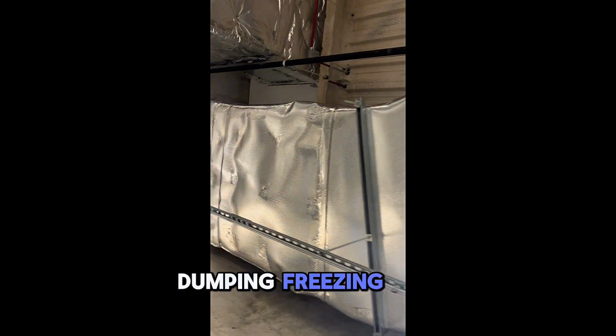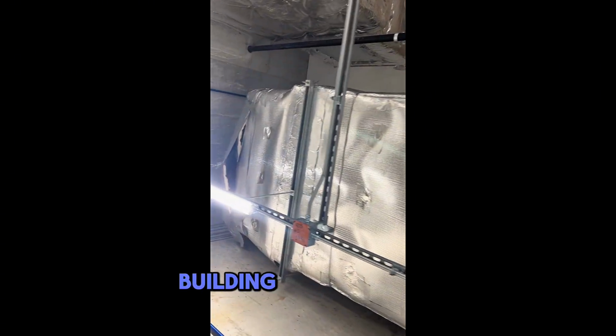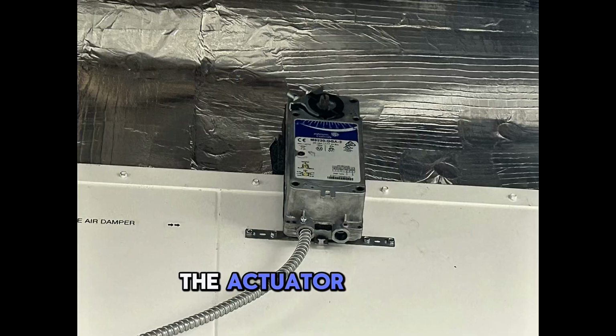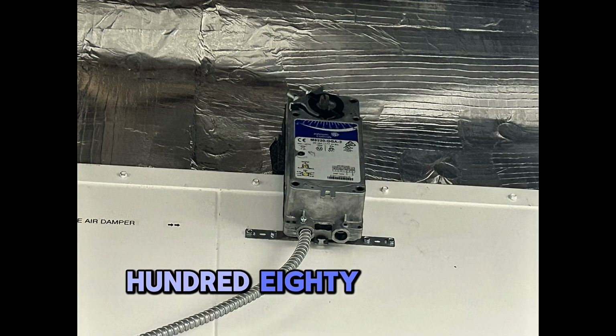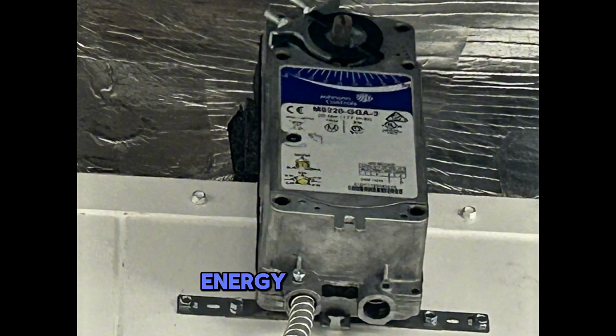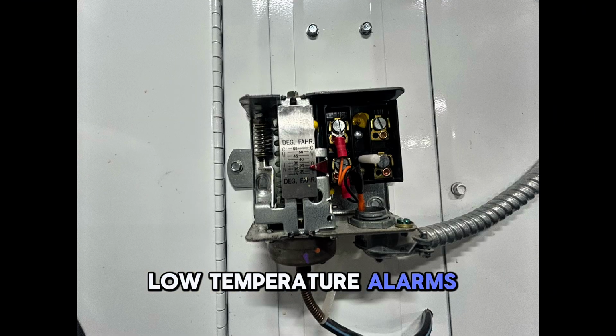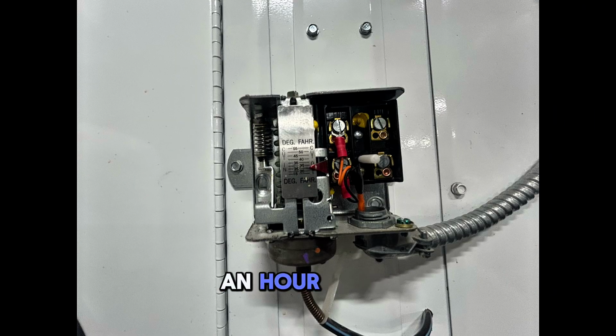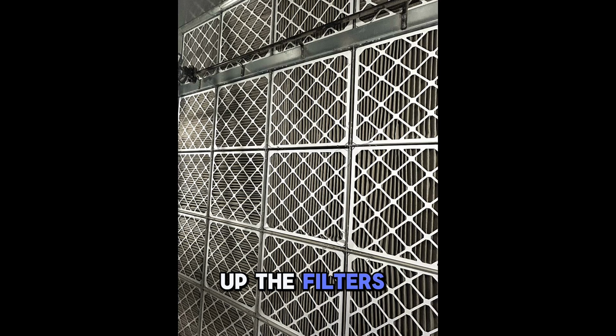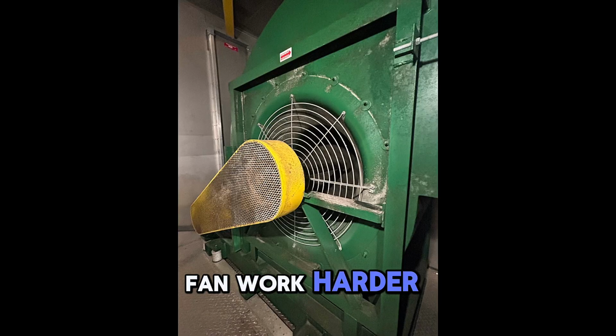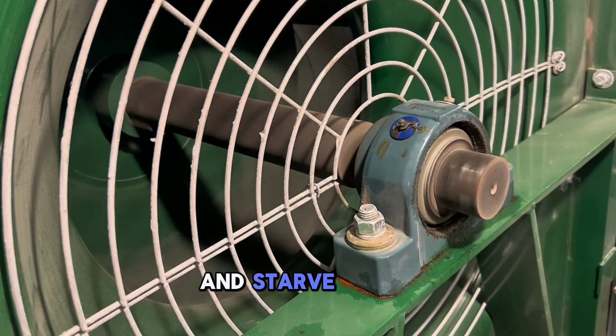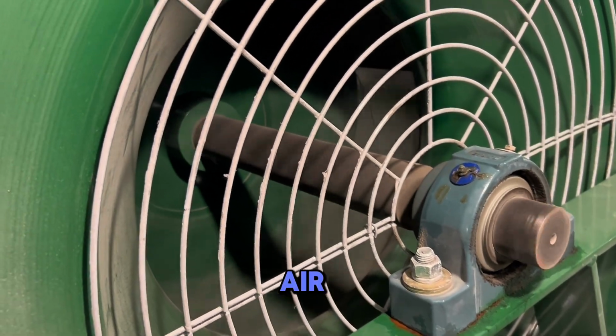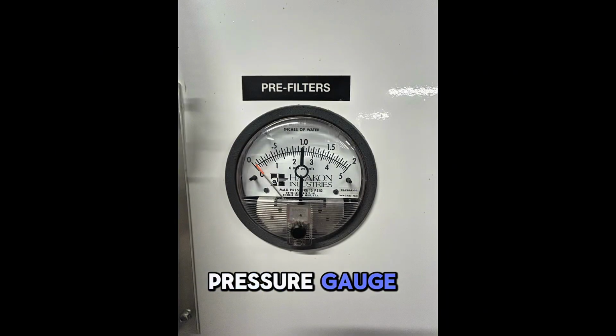On one job, a stuck outdoor air damper was dumping freezing air straight into the building every night. The actuator failed months earlier, a $180 part, months of high energy bills and low temperature alarms. It can be fixed in under an hour. Next up, the filters. Dirty filters are silent killers. They make the fan work harder, raise energy costs, and starve your VAV boxes of air. Watch the differential pressure gauge. When it gets too high, you already have a problem.